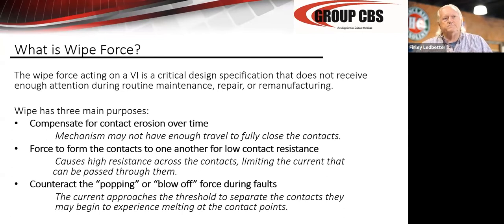This pressure is very important because when you have a through fault or you have an event, it stops the contacts from popping. So let's just say that you have a through fault and the breaker pops. When it pops, it opens all three phases, or one phase or two phases randomly, meaning they don't operate in sequence. When they do that, you develop ferroresonance problems throughout your plant that damage transformers, damage motors, twist cores, twist cables, flop cables, break splices, all sorts of things happen when you get an imbalance. That's why breakers have to be timed to where they open and close within 2 milliseconds of each other, so you escape this ferroresonance issue.